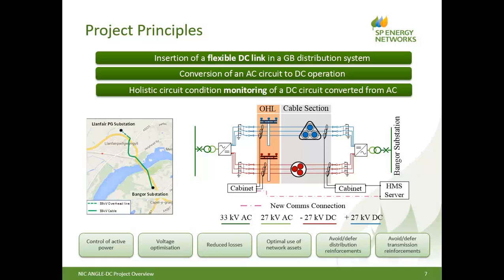And this is the HMS, which is short for Holistic Monitoring System. What this is really all about is for us to look at the signature footprint of the cable in terms of partial discharge, and try and understand the level of the health position of the cable, and for us to continue monitoring it following its DC conversion, and that will give us an opportunity to see whether there's any further deterioration of the cable insulation through the operation under DC.